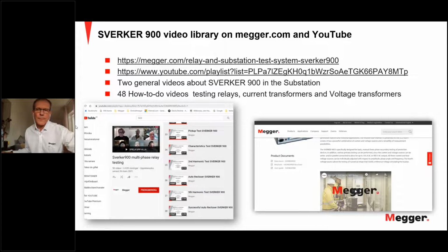Okay, another one. What procedure to test overcurrent protection relays by Sverker could be done? I mean, it's depending on what kind of relay you have. Actually, Sverker can do all of the tests because you are running the generators, current and voltage. You can change the frequency, you can also change the phase angle, and so you can create whatever you would like to do. The only thing is when you're testing complicated relays, you don't get that much help in calculations. So you need to be skilled at doing the calculation by yourself.